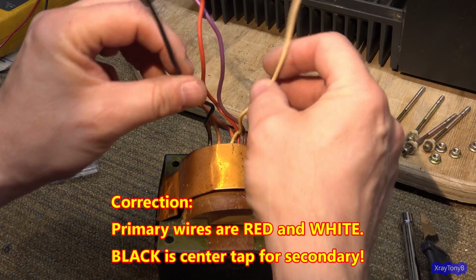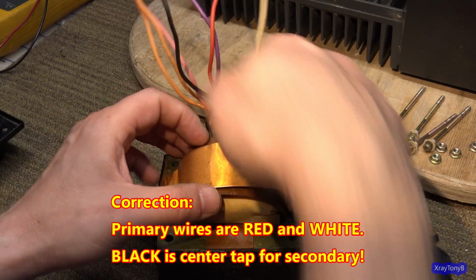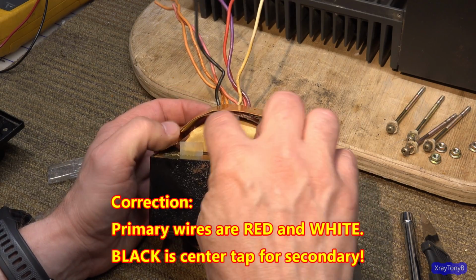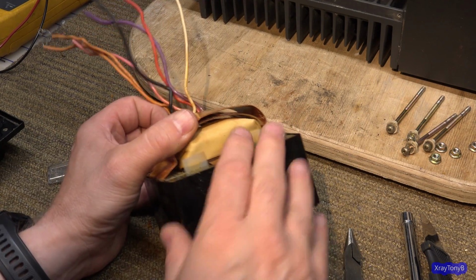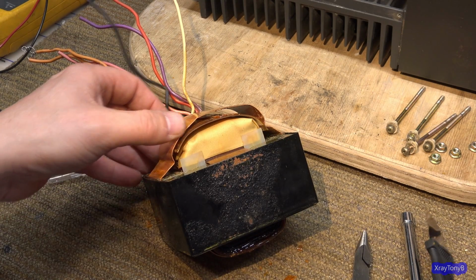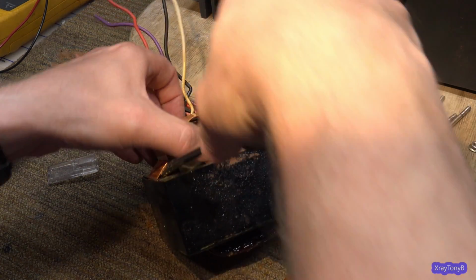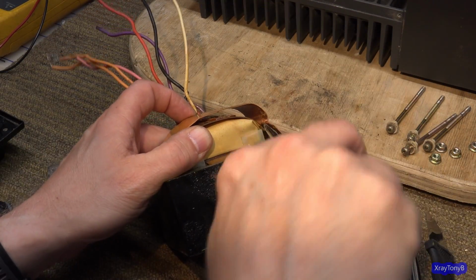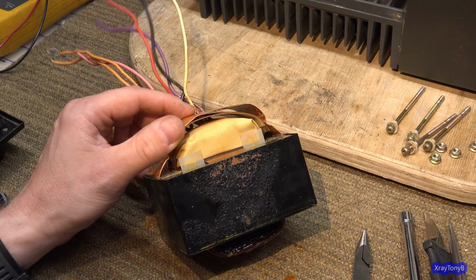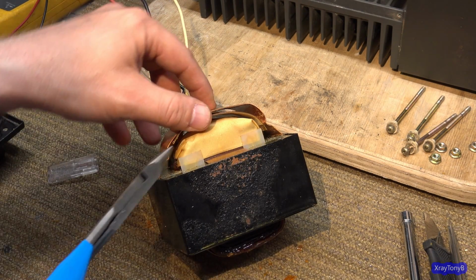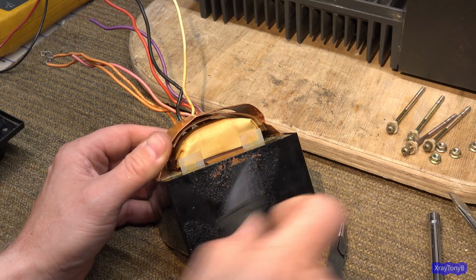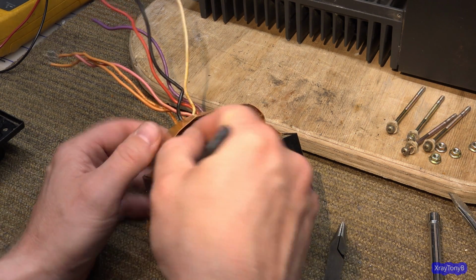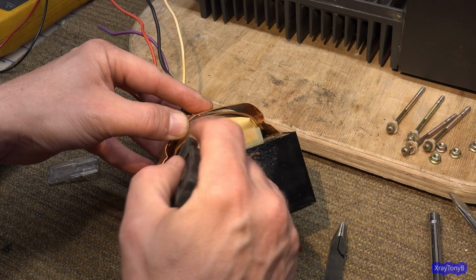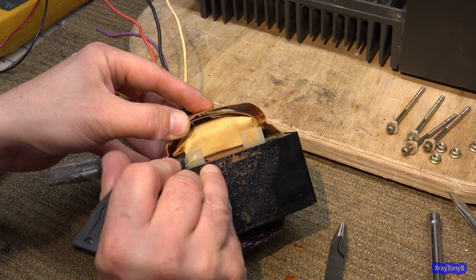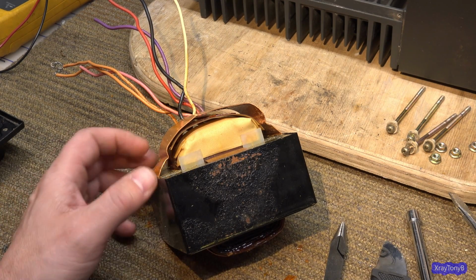The primary wires are these two right here, and they go onto this end, and I can see them bending over. What I cannot see yet is any type of thermal fuse, but that doesn't mean there isn't one in here, and it doesn't mean that it's just not down in there a little bit further. I don't want to have to tear this whole thing apart if I don't have to, unless it's really necessary. I'm just using some different flat tools to kind of pry open some of this varnish, because this is a varnish dip transformer. This is actually a really well built transformer.